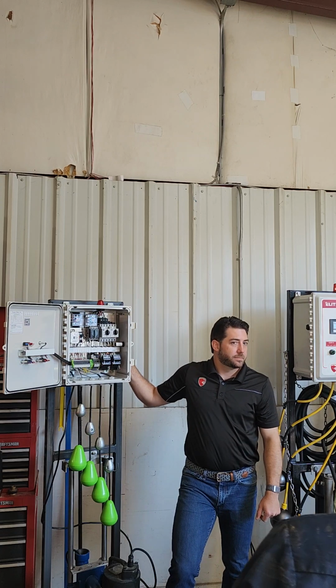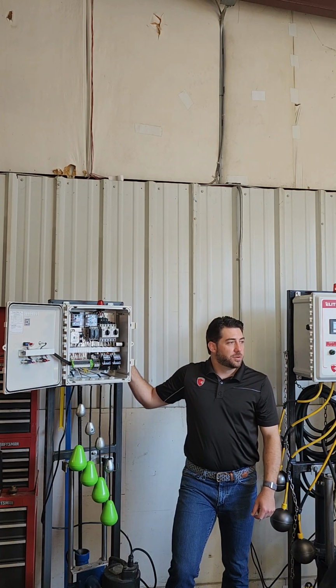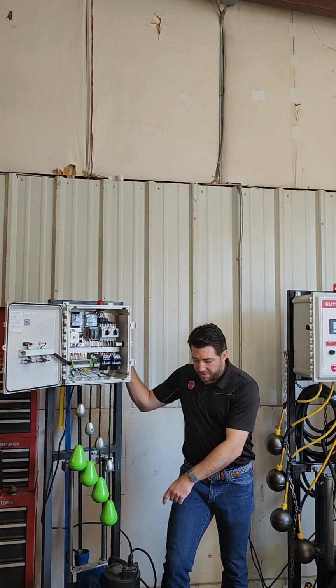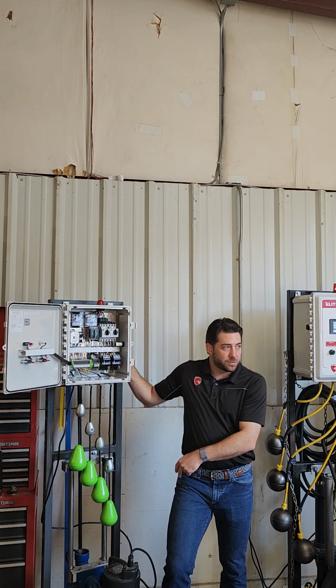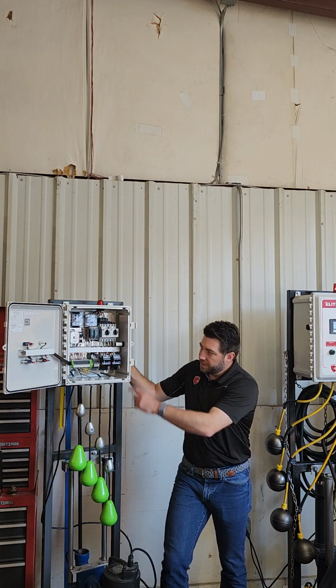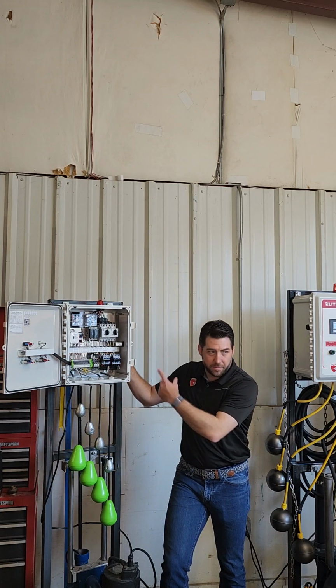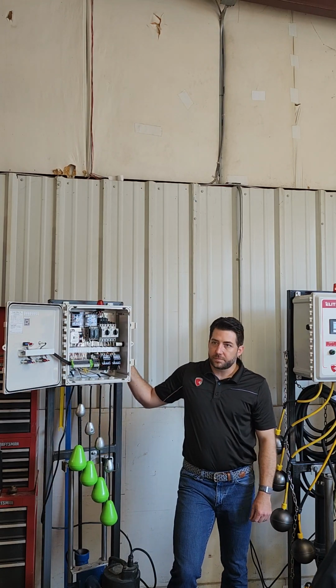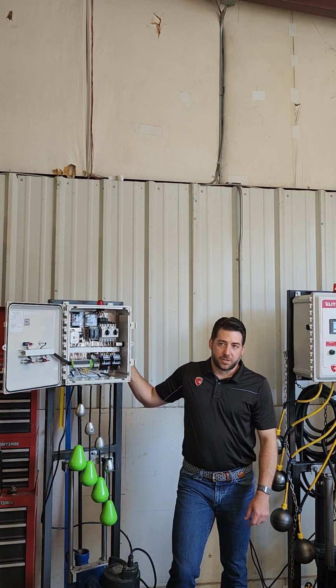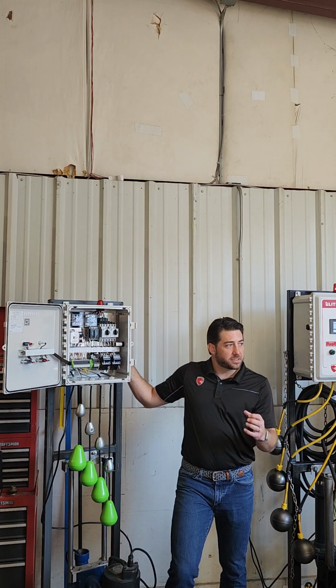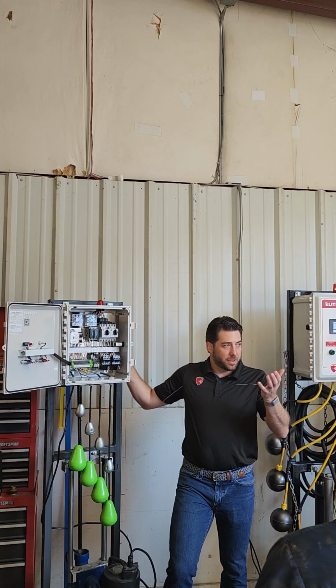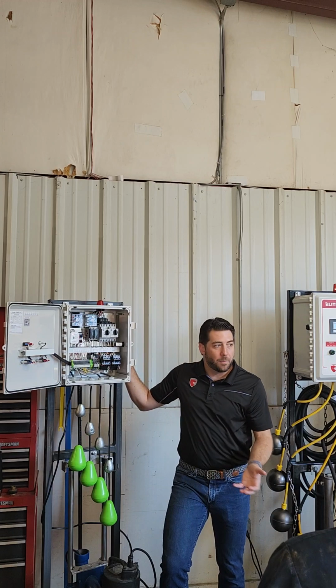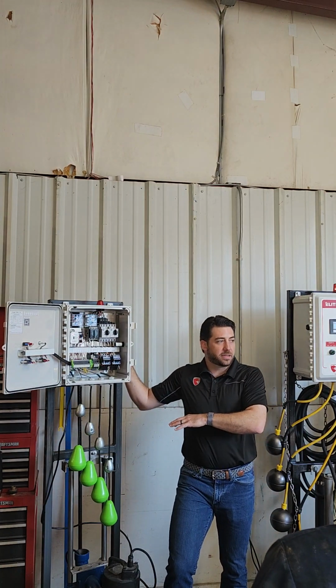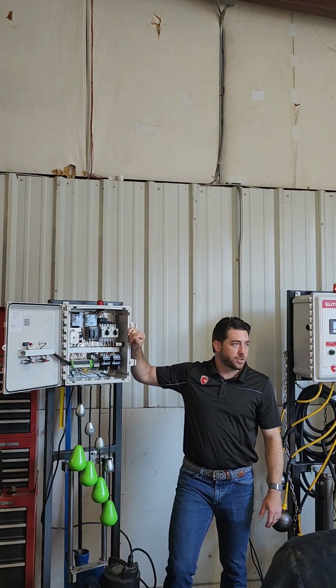Right. Or something stuck in there, right? Well, a direct short would typically be that it's going to ground somewhere, so either inside the windings or in the wiring between them. When it's got something stuck, it takes a little bit before it trips the breaker. If it's got something stuck, then the amps are going to overload, and how long it takes to trip depends on how much it's overloaded.